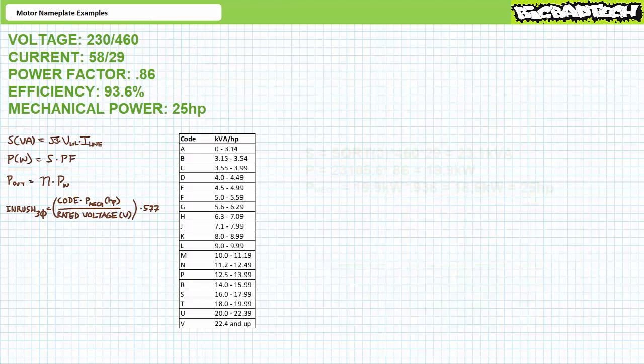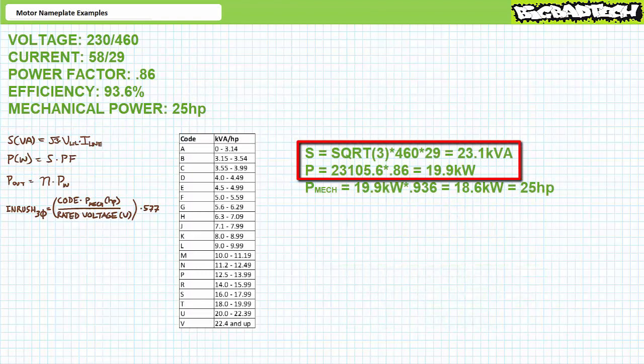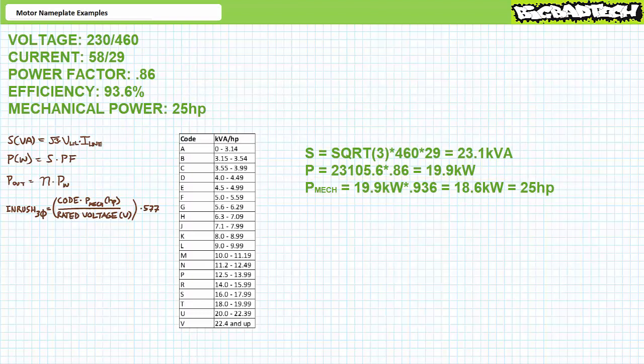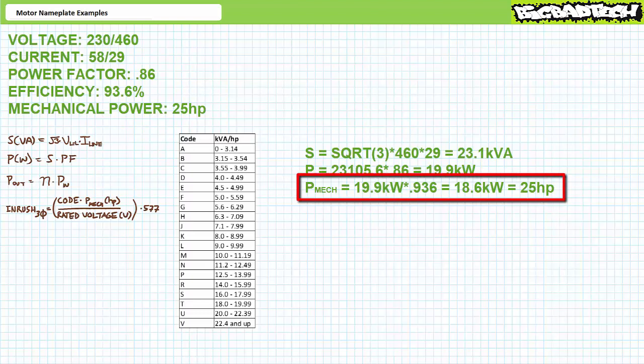If you're tracking, you should obtain the following data. Substituting the given values into the apparent power formula gives apparent power input of 23,105.6 volt-amperes, or more appropriately 23.1 kVA. Substituting into the real power formula gives 19,870.8 watts, or more appropriately 19.9 kilowatts. Note that at rated condition the motor operates at 93.6% efficiency. Rearranging the efficiency formula, output equals input times efficiency, giving 18,599 watts or 18.6 kilowatts — roughly equivalent to 25 horsepower, extremely close to the nameplate mechanical power.